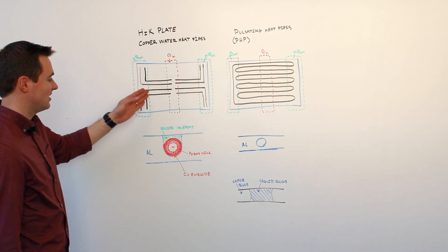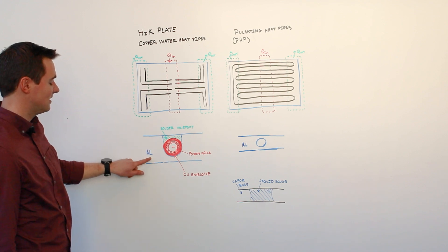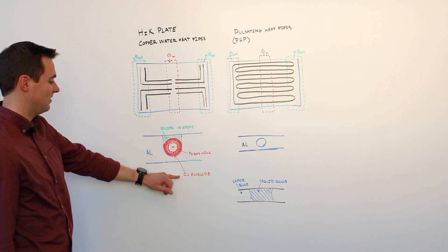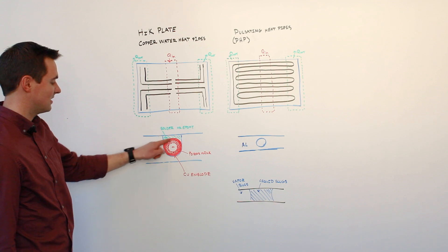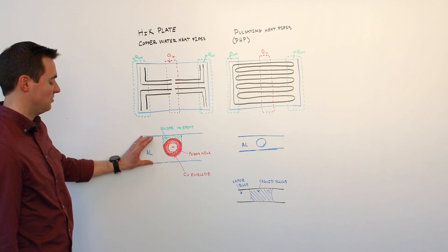If we look at a cross section, what you would see is that we would typically have an aluminum plate with an embedded copper heat pipe which is comprised of a copper envelope with a porous copper wick structure. That typically is soldered or epoxied into the plate.